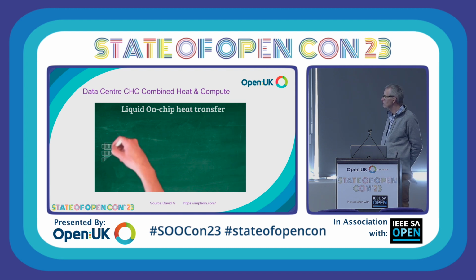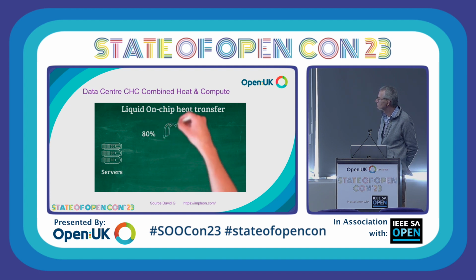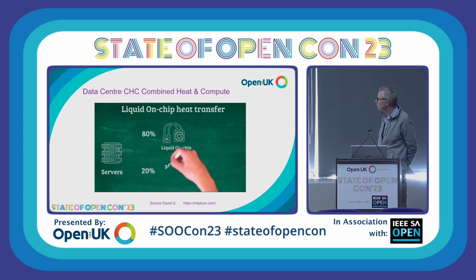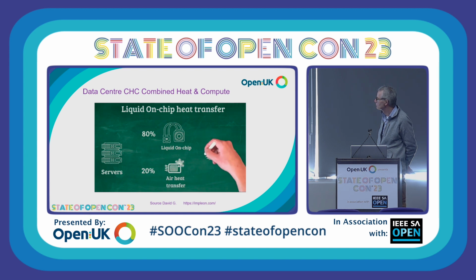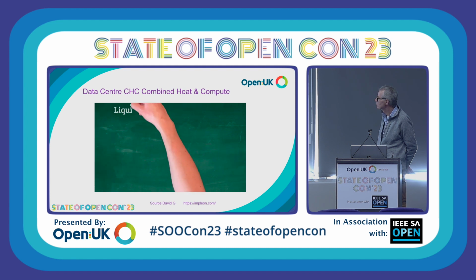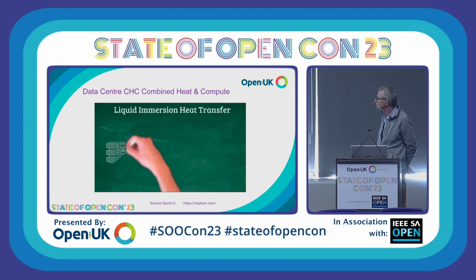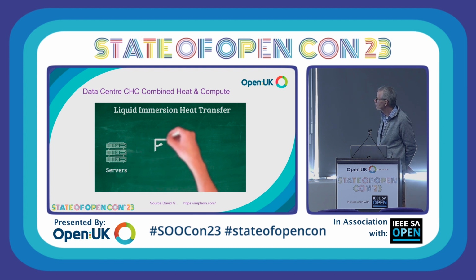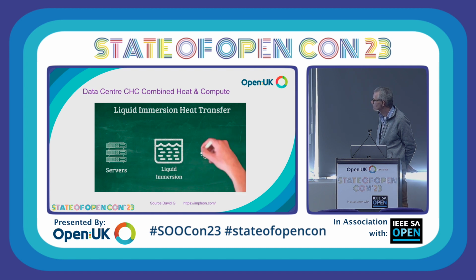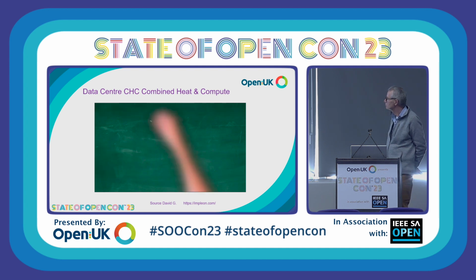With liquid on-chip heat transfer in well-managed IT servers, 80% of the heat rejection can be taken out from the chips and the rest 20% by air in conventional mode. The liquid from on-chip solution with temperature 55-65 degrees can be directly used by householders. The liquid immersion solution uses servers without fans, fully immersed in liquid, and the heat rejection from all components is transferred to users with temperatures 45-60 degrees. In conclusion, I want to deliver the message that combined heat compute is the way for including data centers in a circular decarbonized economy.